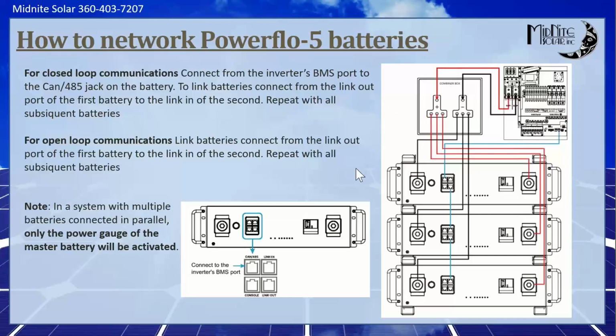Like in this picture, these could all be small gauge wires going to this combiner, say number 2 wires, with a 2-aught or 4-aught cable going to the actual inverter. If you daisy chain these together, all your cables have to be the larger size. If you stack 4 of these up and run to this combiner, then stack 4 more and run to another combiner, each stack is delivering half the power. So that's what you have to look at, how the power is being divided. I personally like using our lithium battery combiner and running each battery back to it, but sometimes that's not practical, so you do what you have to do.